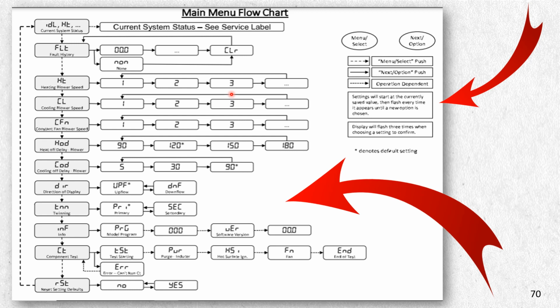And then make sure you write that down, because that's what you're going to have to set the new one up for. So let's say you're not using the cell phone and you're going strictly by the manual display. So you're going to see your idle, which is your current status. It may say HT for heat. Then you're going to go down, you'll have your fault code, and it'll tell you which fault code you have. You can clear that out.